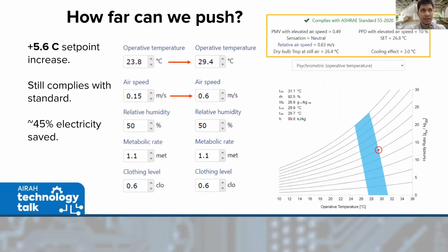I said initially that fans can provide up to 6 degrees of perceived cooling. So let's push this to the max, right? I increase the set point by 5.6 degrees. It still complies with ASHRAE 55, and with bigger electricity savings, about 45% here. So that's how fans can help with energy efficiency and energy savings.